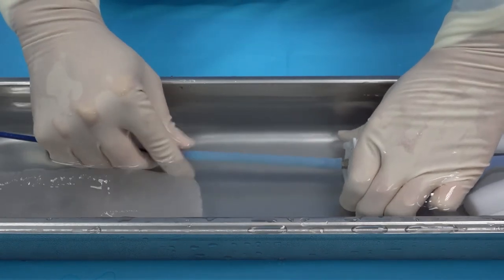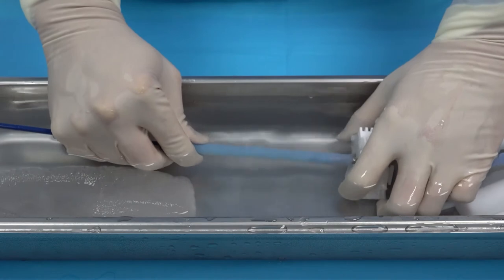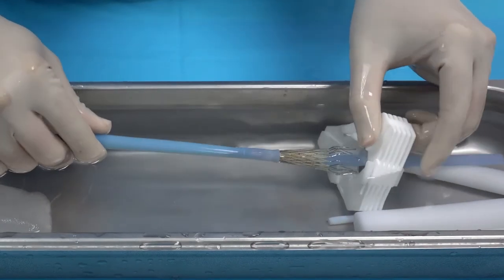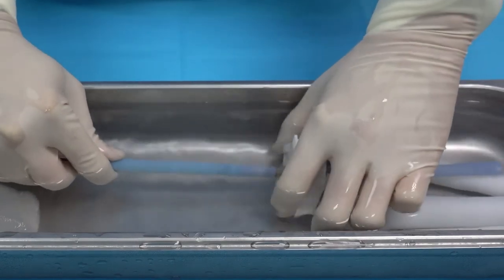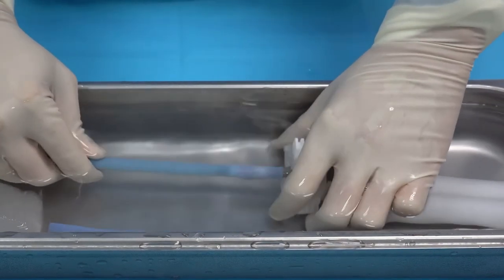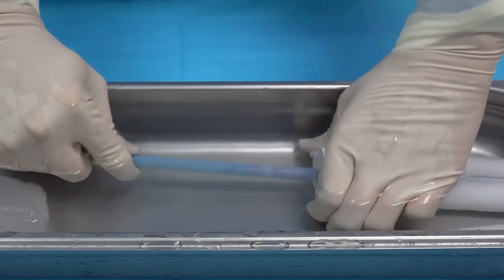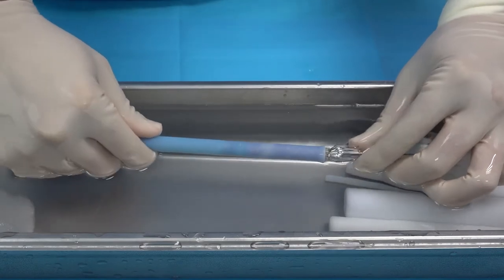Repeat to crimp the P-valve more distally with the left hand and advance the loading tube with the right hand until the loading tube is advanced over half of the P-valve. Check the P-valve for any infolding by rotating the delivery system. Repeat the process of crimping and moving forward the loading tube until the bare flared outflow end frame. Check whether the bare flare frame is overlapped or not, and straighten if necessary.